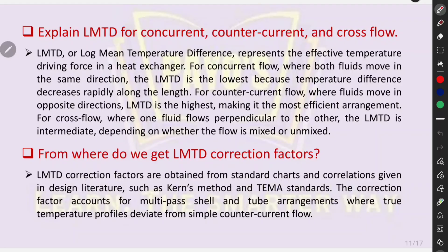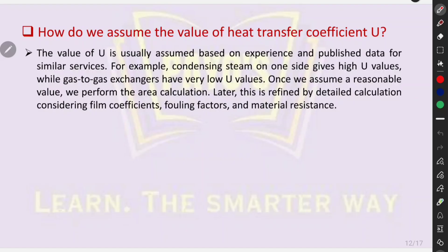From where do we get LMTD correction factors? LMTD correction factors are obtained from standard charts and correlations given in design literature, such as Kern's method and TEMA standards. The correction factor accounts for multipass shell and tube arrangements, where true temperature profiles deviate from simple counter-current flow. How do we assume the value of heat transfer coefficient U? The value of U is usually assumed based on experience and published data for similar services. For example, condensing steam on one side gives high U values, while gas-to-gas exchangers have very low U values. Once we assume a reasonable value, we perform the area calculation, which is later refined by detailed calculation considering film coefficients, fouling factors, and material resistance.